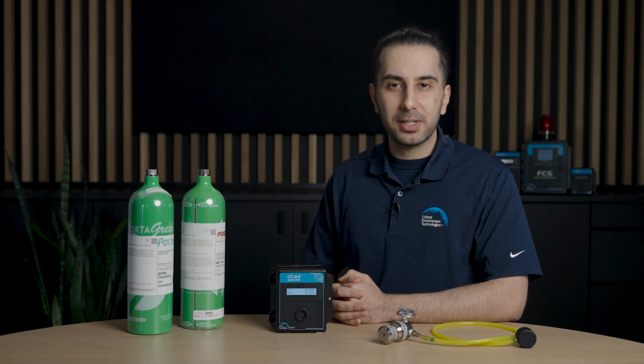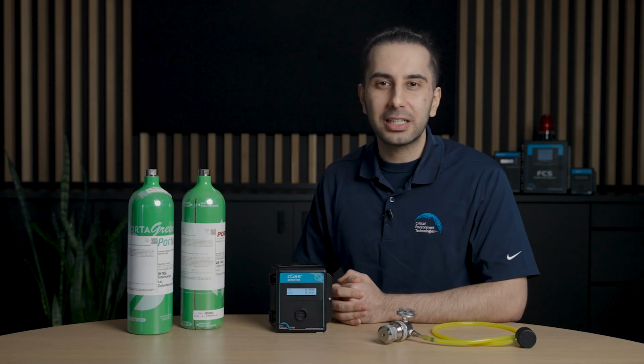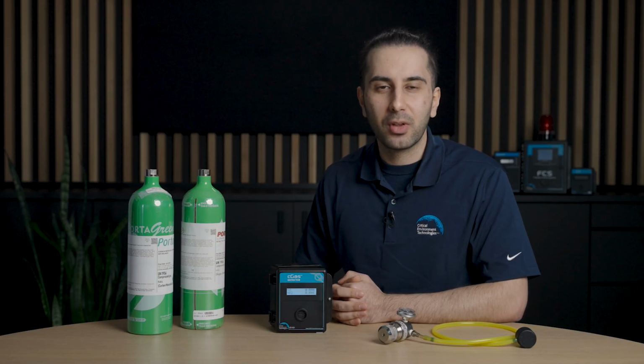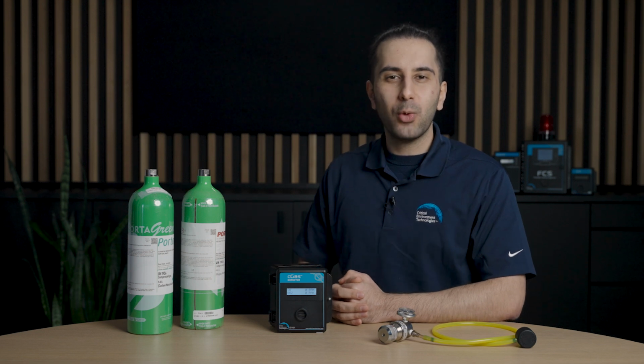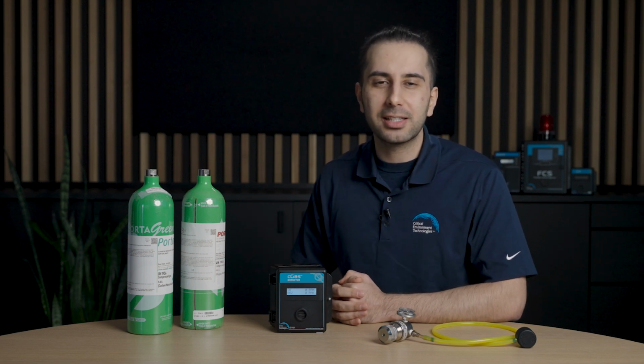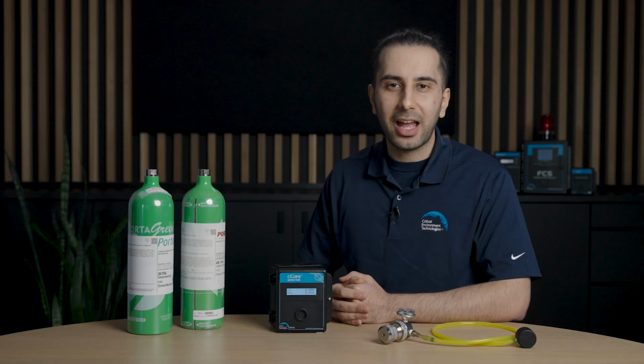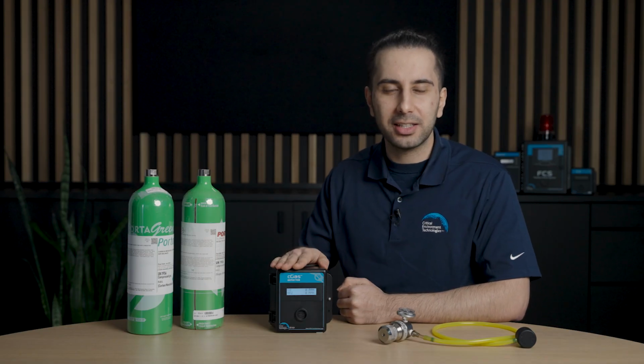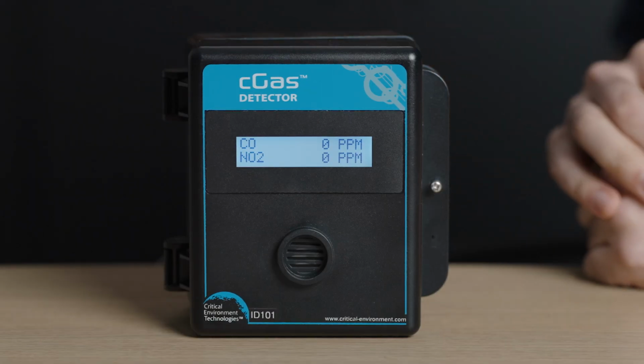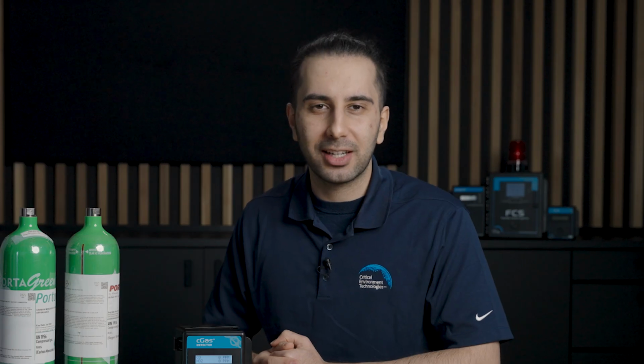Calibration is typically done in a similar fashion for most gases. However, there might be specific requirements depending on target gas or a sensor type. For the purpose of this demonstration, we will perform a carbon monoxide sensor calibration. Here, I have a digital carbon monoxide detector. The procedure is the same for the cGas A analog detector.